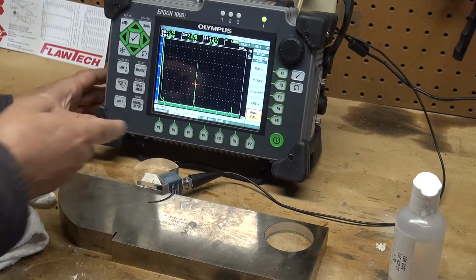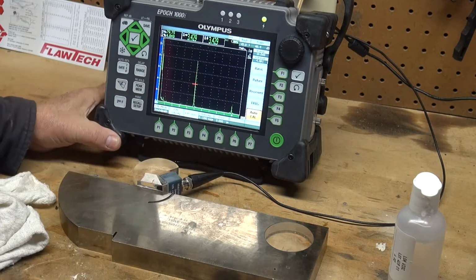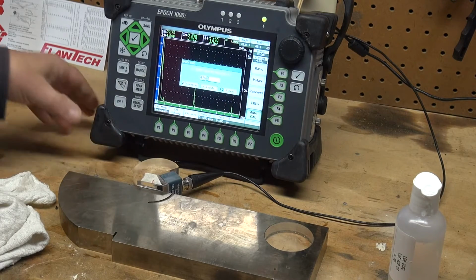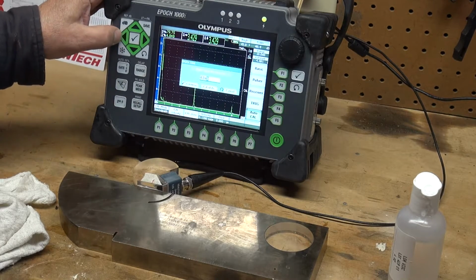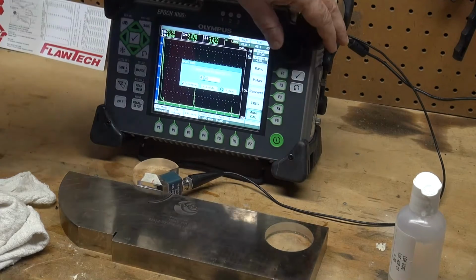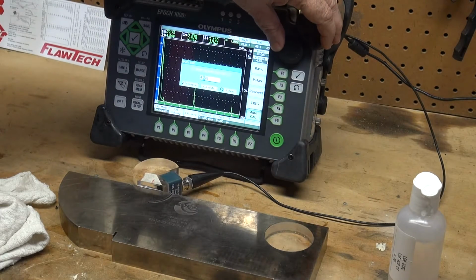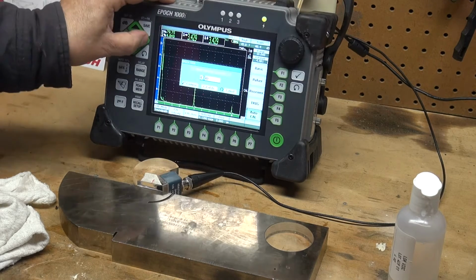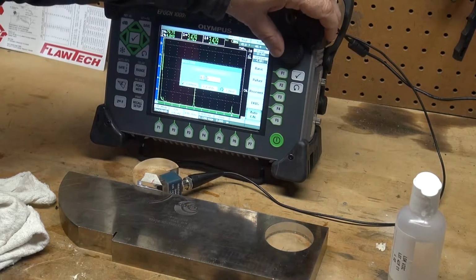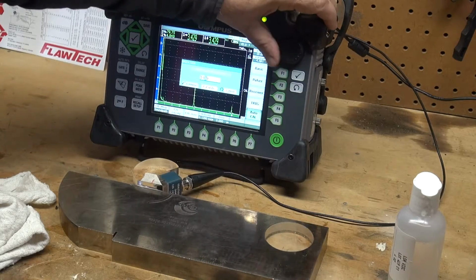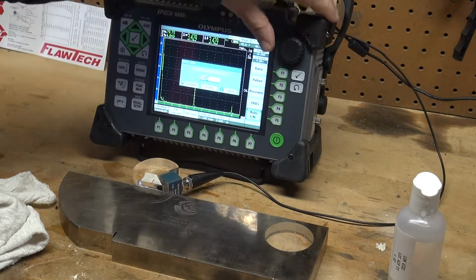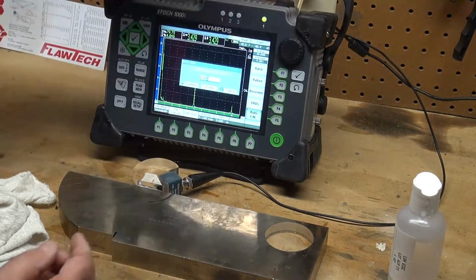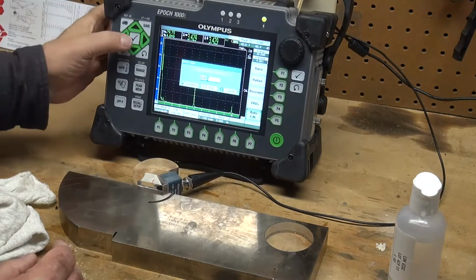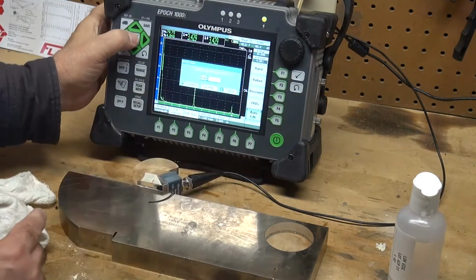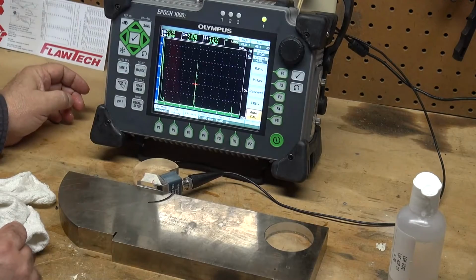The first thing I want to do is cal 0, press that button, and I have to tell the tester that it is looking at, in the gate is captured, a 4-inch sound path. So I change that to 4 inches, and here we go, 4 inches. Hit the check button. I can hit it here or here. It will store that value.